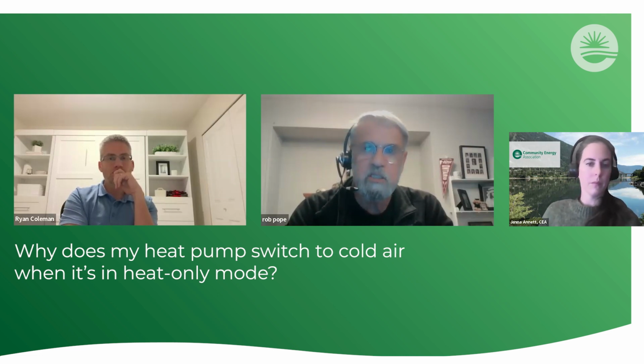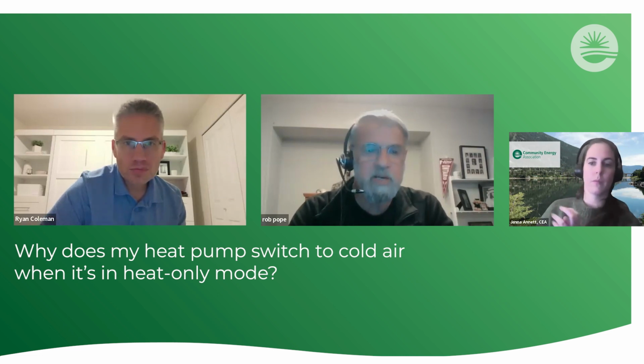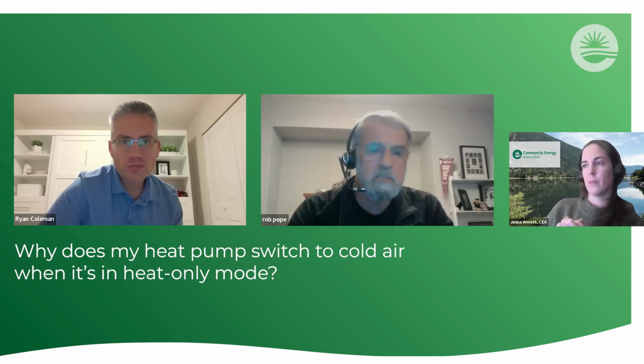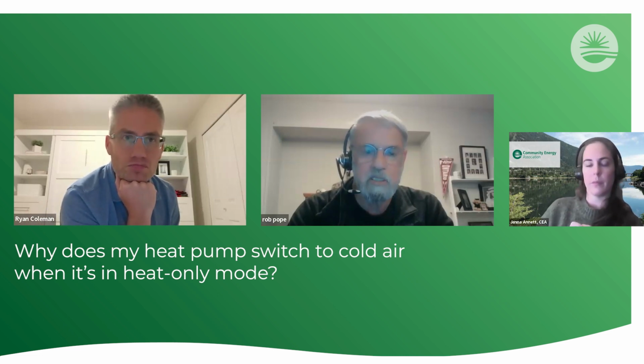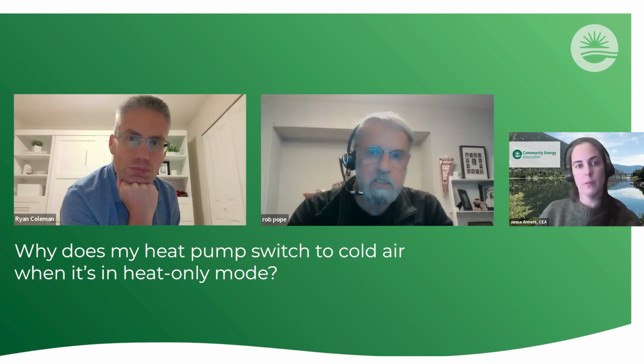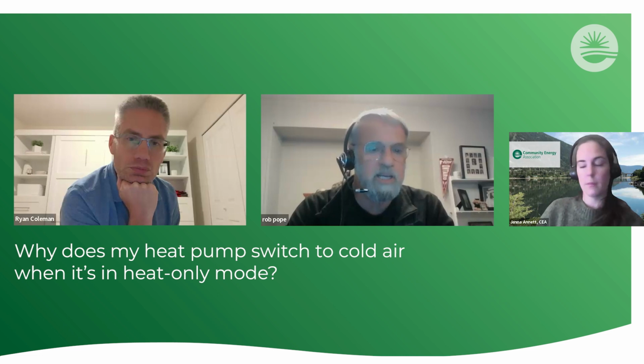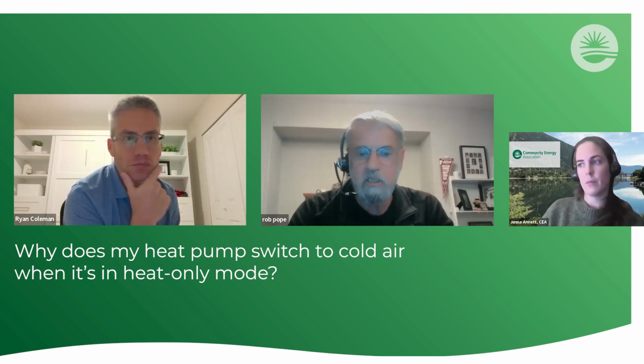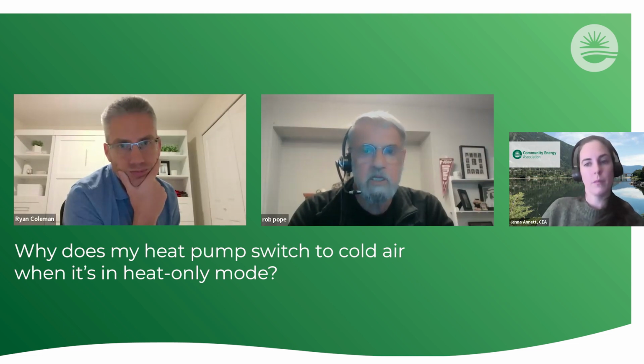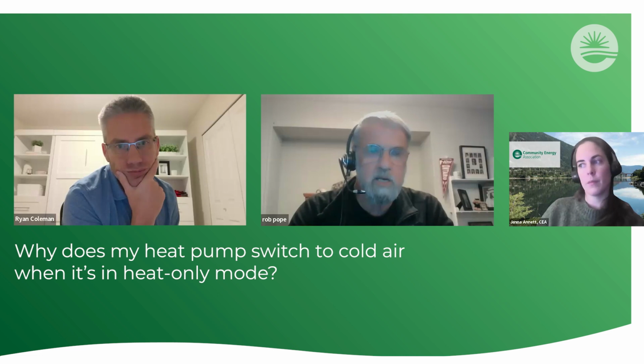The only other potential answer to that is that the fan is running in continuous fan mode or fan on mode. In which case, when there's not a call for heat, you will feel your ambient air temperature, which may feel cold to the touch, circulating around the space. So if the fan is in its on cycle, which we always recommend, it's room temperature air. It's not heated air. That may feel cool to the touch, but if your thermostat is on heat only mode, it's not going to bring on cooling. If it's in heat only mode and fan is on mode as opposed to auto mode, then when there's no call for heating it'll just be recirculating air, which may feel cool to the touch.